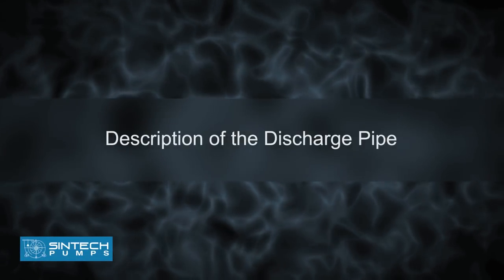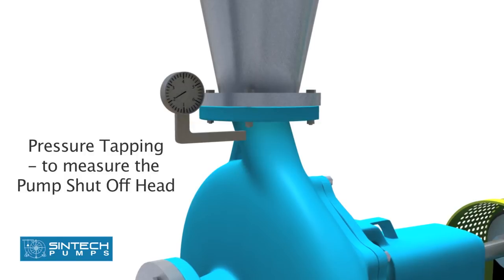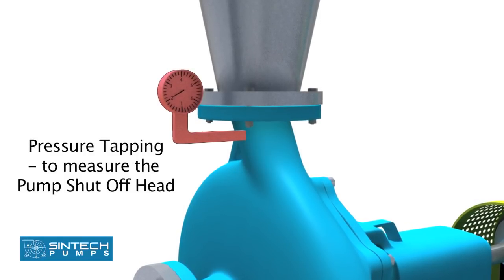Description of the discharge pipe. There should be a pressure tapping as close to the pump outlet and before the isolation valve as possible to measure the pump shut off head.